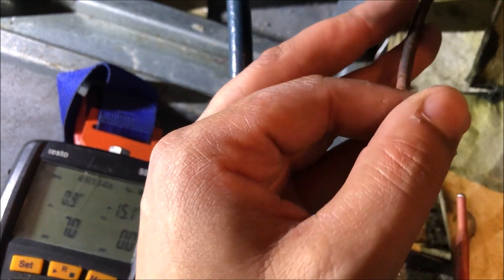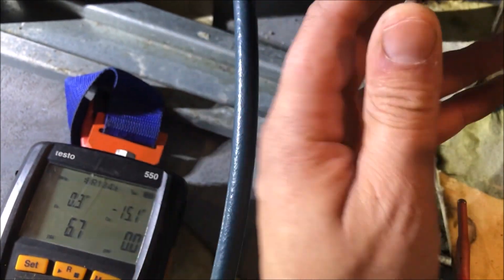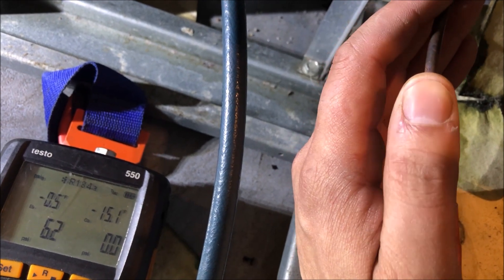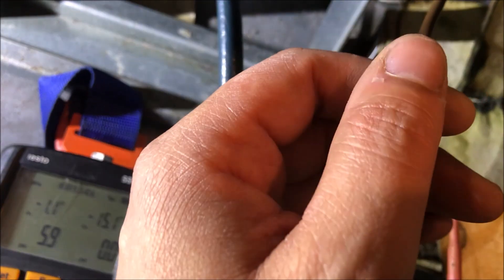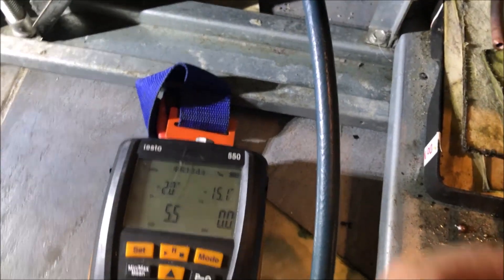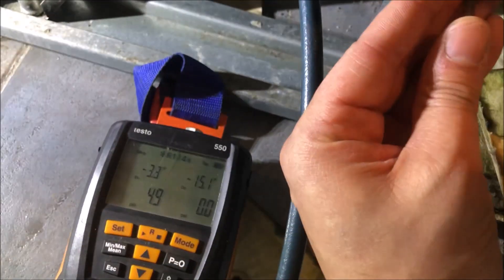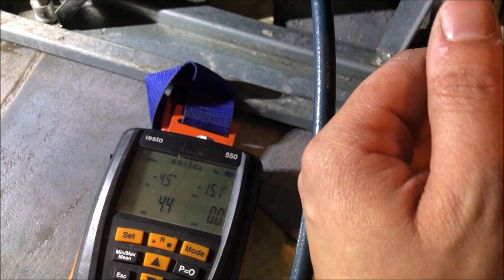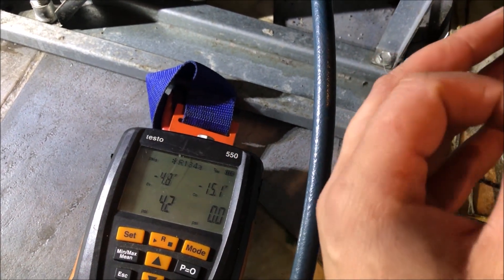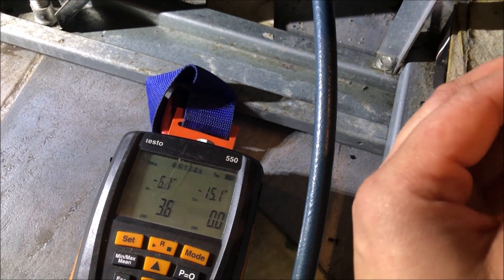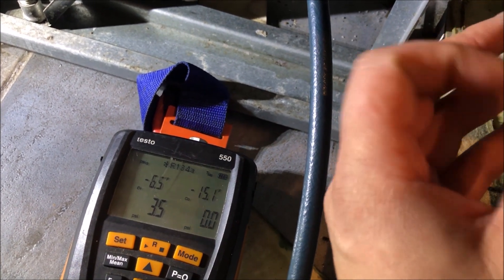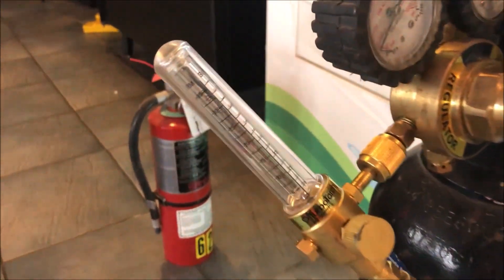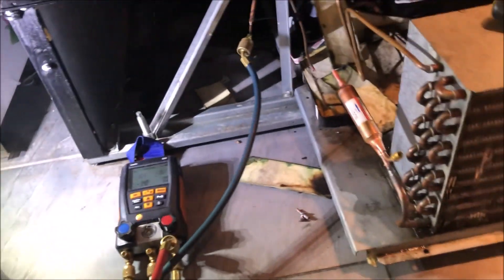What got in the cap tube, it's hard to say. Sometimes when our condensers are plugged, it'll make sludge in the system and then that'll plug up the cap tube. Could be from someone brazing without flowing with nitrogen. There's all kinds of factors why this cap tube can get plugged, but if the system hasn't been opened up in a while, it's usually because the condenser was plugged and we've just made sludge in the system and it got stuck in the cap tube. So we're gonna go ahead and braze in our cap tube back in our filter dryer. Make sure you're flowing with nitrogen, especially on these little cap tubes. It is super important.